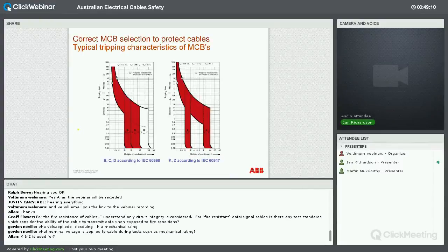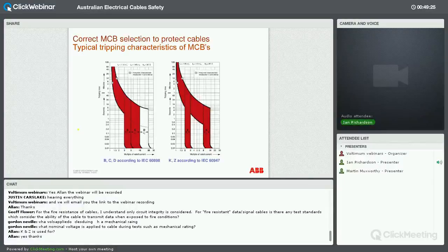There's a question come up from Alan: what's the use for K and the Z? Hopefully I just answered that. As I say, the Z curve commonly will be used for electronic protection because of the speed of operation, and the K curve, certainly in Europe, is more commonly used for either motor protection or transformer protection.